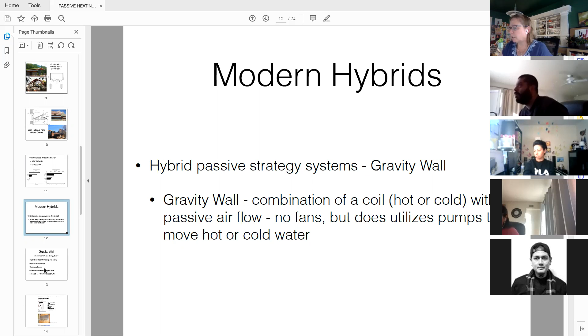It's called a hybrid because it's not strictly passive. It needs either hot or cold water in a coil to help create the convection that will move either hot or cold air. So the energy aspect of it is in making the temperature of the water hot or cold, and the energy to run a pump. But it's a true gravity wall, it does not have a fan. Some I've seen have added fans to assist, but you don't need them. However, like any passive system, it's not fast performing. It needs some time in order to let the natural convection of the air create thermal comfort in the space.